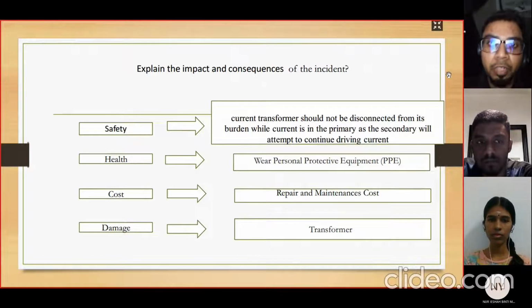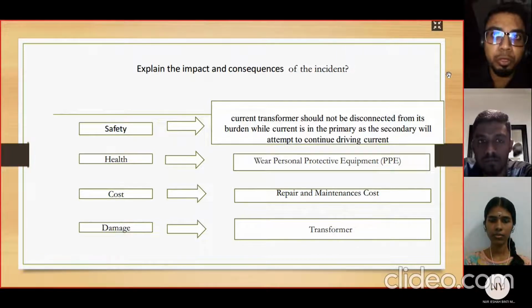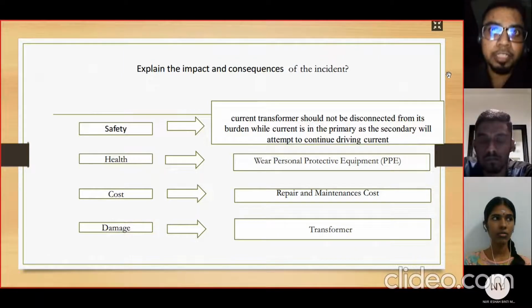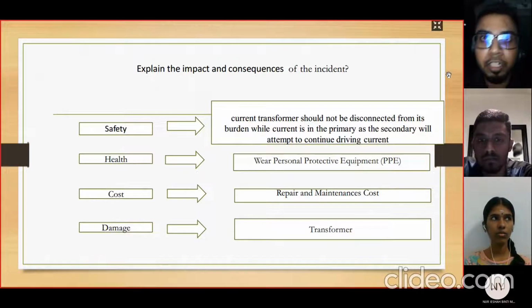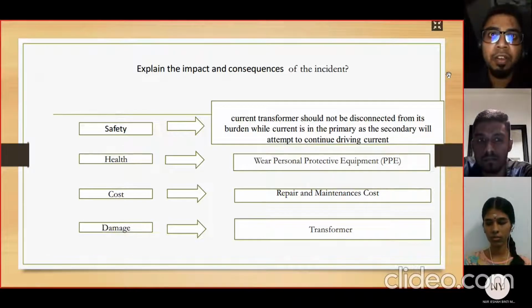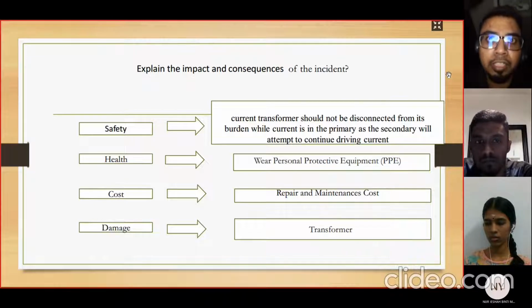Explain the impact and the consequence of the incident. Safety: the current transformer secondary should not be disconnected while the current is in the primary, as the secondary will attempt to continue driving current. Next is health. Wear personal protective equipment so that it can prevent damage to our health when working in a hazardous environment.